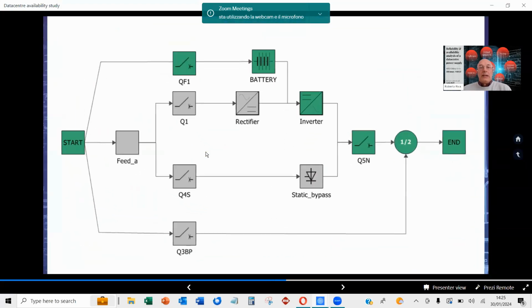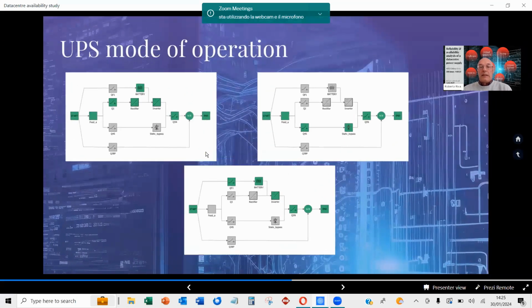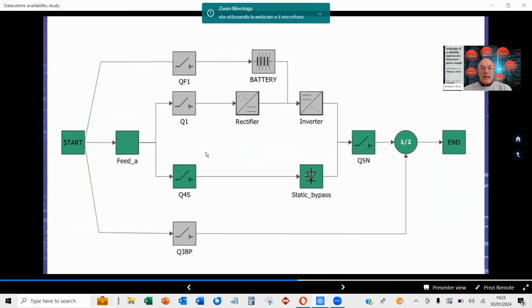Then we have the case where the UPS main is not working, so we feed via the batteries, providing power via the battery—though obviously the battery has a limited life. Then we have the bypass, in case the main or the battery are out of use for whatever reason, giving us an alternative supply via the bypass.